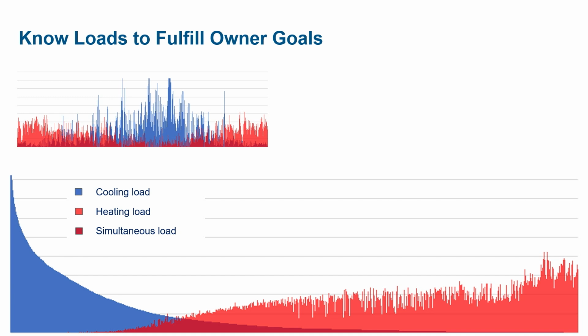cold outside. Reheat for multiple zone VAV systems, tempering supply air for off-design zones, or dehumidification in humid hours represent typical coincident loads. Knowing the maximum coincident load informs the necessary capacity for heat recovery. Don't buy more than is required. Peak loads determine equipment capacity required for heating and cooling.